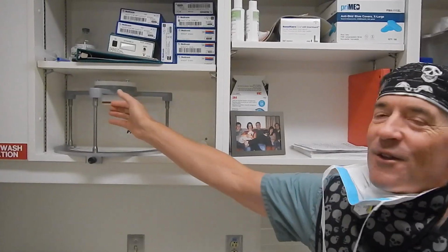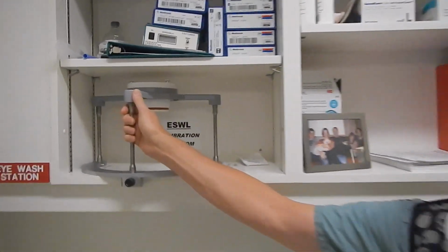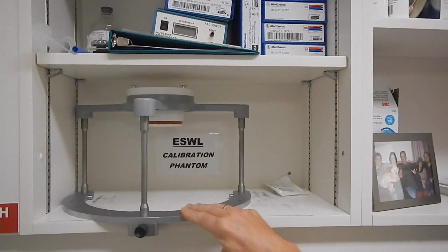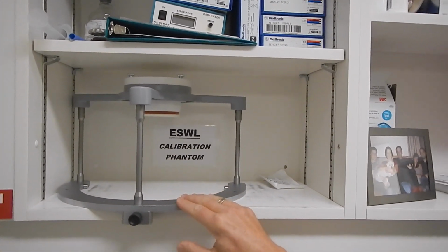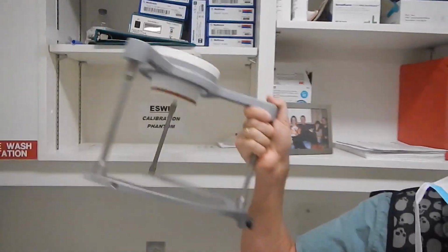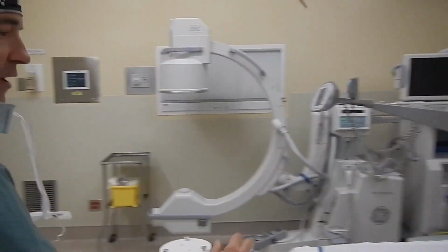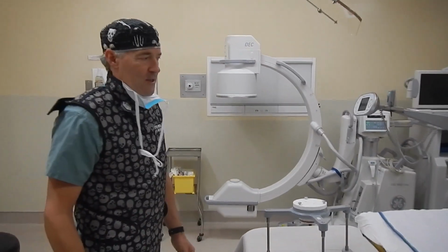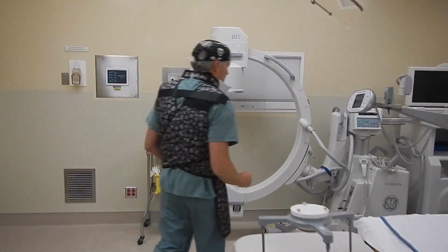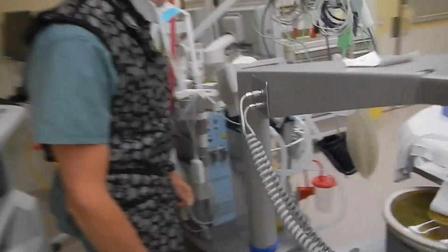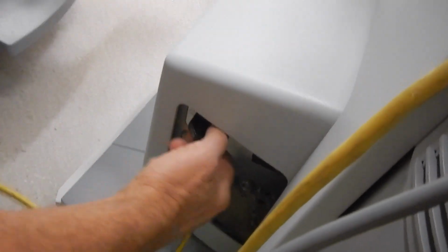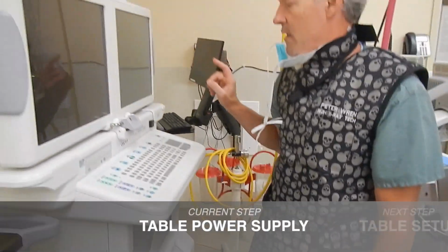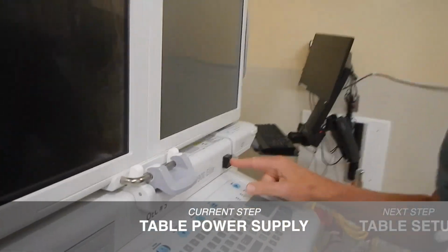Today we are going to calibrate for an ESWL. So the first thing we do is grab the Phantom, which you'll see how important it is for this process. This is the ESWL cable. First thing we need to do is turn on the power, which is right down here. It goes clockwise. And also the C-arm that's used for these gets turned on.